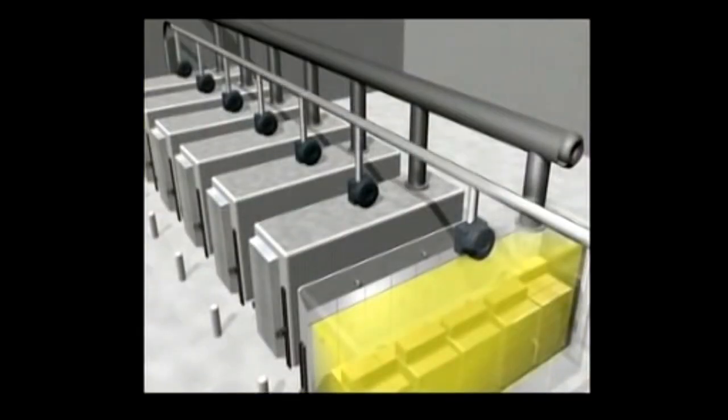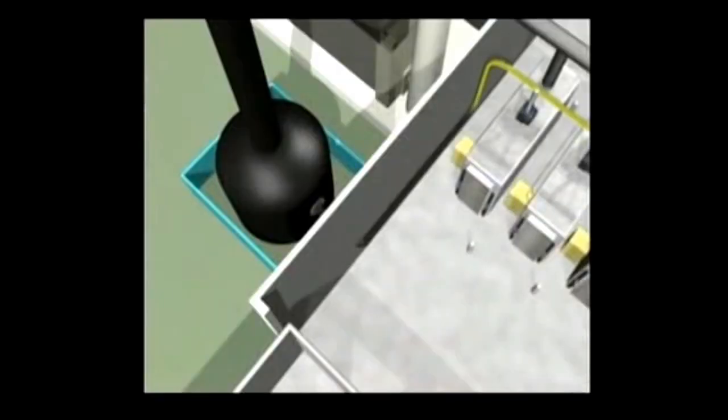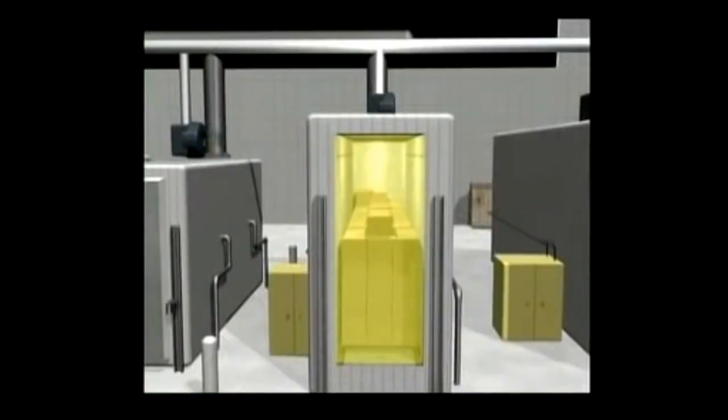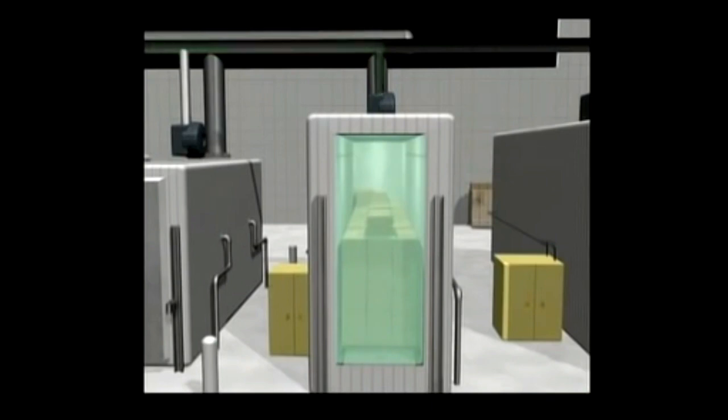After the sterilization phase, ethylene oxide is removed from the chamber and the packaged products in several steps. First, about half the gas is pumped from the chamber to a pollution control device called a scrubber, where it is removed by chemicals. Next, virtually all of the remaining ethylene oxide is removed in a step called gas washing. This involves injecting air and nitrogen into the chamber where they mix with the ethylene oxide. This mixture is then pumped from the chamber to the scrubber. This process is critical to reducing the concentration of ethylene oxide to below explosive levels, and is repeated several times until there is only a trace amount of ethylene oxide remaining.